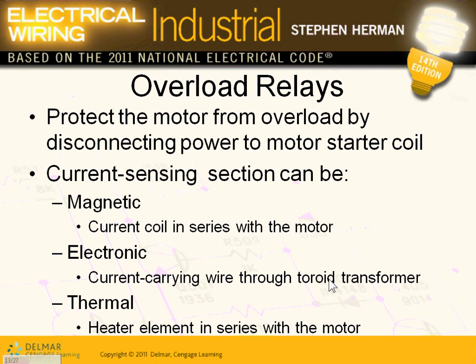Unfortunately we don't do the control here in this class. Different types of overloads: the cheapest, easiest way is a heater. You let the current go through a heater, it heats up, and physically and mechanically pushes two contacts open. The better one is the electronic overload — you can sense the current has gone from 50 amps to 150 amps and electronically make a decision to open, close, or alarm.